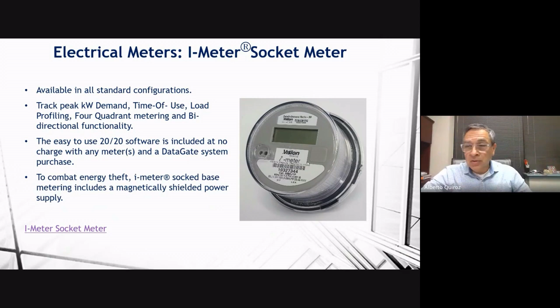All these meters are good for 600 volts, so you don't have to worry about doing a 600 volt system. They're all Measurement Canada approved, so you can use them for revenue. And we can supply them with radio or a Cat M1 modem. So if you've got a pump in the middle of the field and you want to bring in the reading, you can put in a SIM card and the modem and transmit the information of that consumption to a server, and then we can do all that integration on those socket meters.